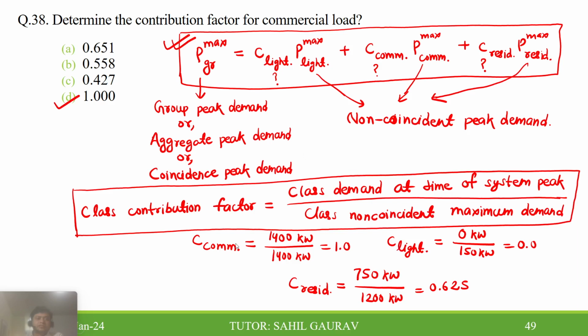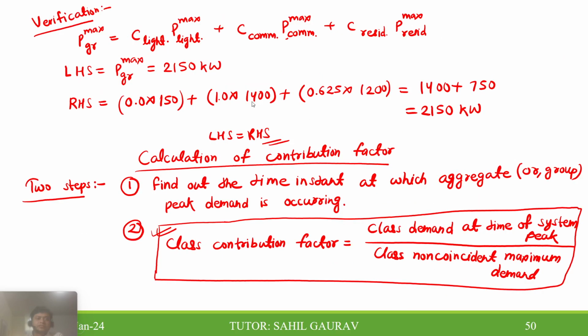Now put all these contribution factors for each type of load in this expression, the one that relates the group peak demand and the individual peak demand. The LHS is the group peak demand, which we know is 2150 kilowatt, and the RHS is the contribution factor of each type of load times its individual maximum demand. You will get the same answer. So LHS equals RHS, which means you have calculated it the correct way.